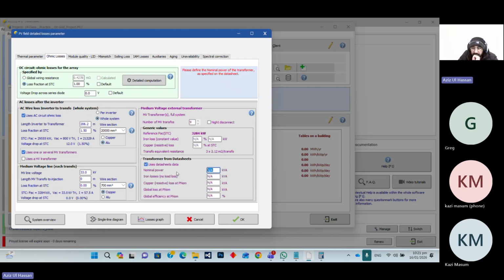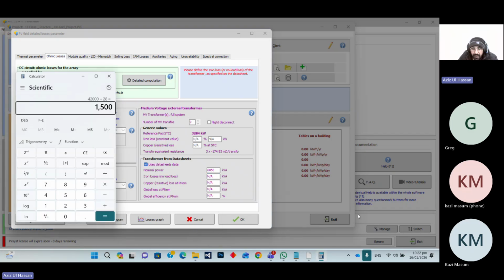Their power is 6.050, sorry, 6.50 kVA. And the length is almost 1800 meters. Like we have 95, 70, 50, this type of voltage drop. I have just explained that you have to get those values from the client, the iron losses and copper losses. But for this transformer, we have these losses from the vendor of that transformer, and they have given me losses of 0.1% for the iron and 1% for the copper.